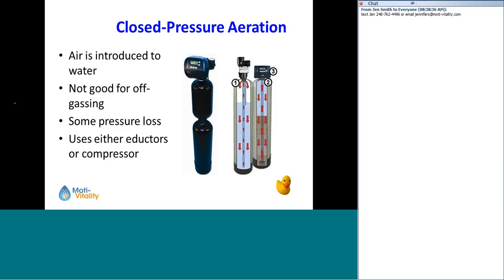The reason they do that is you have to have the contact time. Sometimes they'll use the media itself to help convert iron, for example. A lot of times these will have an air compressor on them. Sometimes there are separate tanks, like here, two tanks stacked one on top of each other. Basically they pump air into one of the tanks, and this is your contact time, and this oxidizes any of the metals in the water.